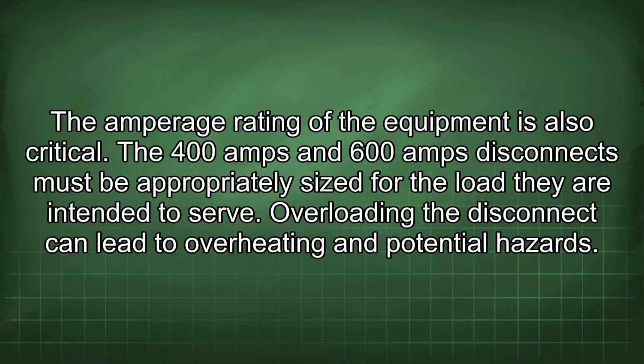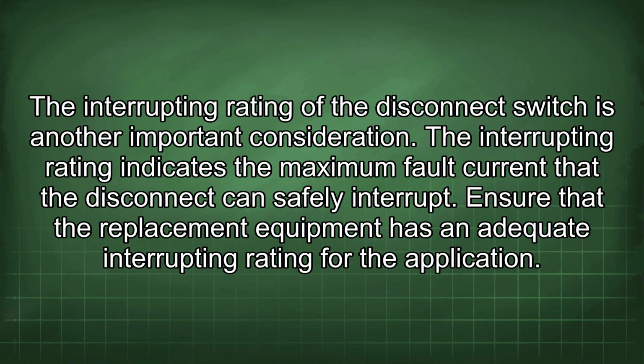The amperage rating of the equipment is also critical. The 400 amps and 600 amps disconnects must be appropriately sized for the load they are intended to serve. Overloading the disconnect can lead to overheating and potential hazards. The interrupting rating of the disconnect switch is another important consideration. The interrupting rating indicates the maximum fault current that the disconnect can safely interrupt. Ensure that the replacement equipment has an adequate interrupting rating for the application.